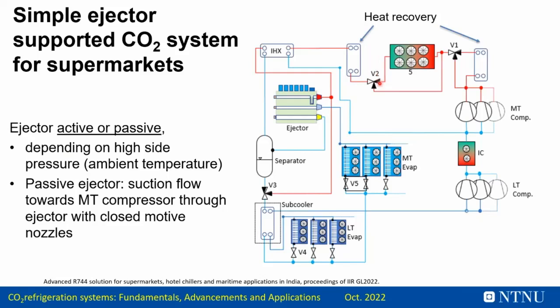In case we have a low temperature at the outlet of the heat rejection, we already have liquid in the red line, so we just close the valve to the ejector and bring the liquid straight to the evaporators. In that case the MT evaporator passes the vapor through the ejector without any action into the separator, and it is sucked into the MT compressors. Yes, this is very efficient and very simple, and the first systems are built nowadays. More information you can find in the proceedings of the Gustav Lorentzen conference, where this concept has also been described more closely.